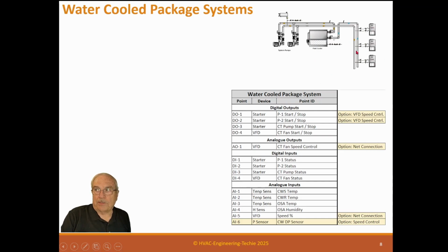So what you do is you put a pressure sensor two-thirds of the way down here, and you maintain whatever PSI delta you need for that, and it'll variable speed these pumps. To do that, you would put a VFD here and a VFD here, so you'd have VFDs on these pumps. You have a speed, and then you have an optimal speed control. Here's the condenser water differential pressure sensor, which would be out here. So you have to add this point, and if you do, these points now become optional to the VFD.